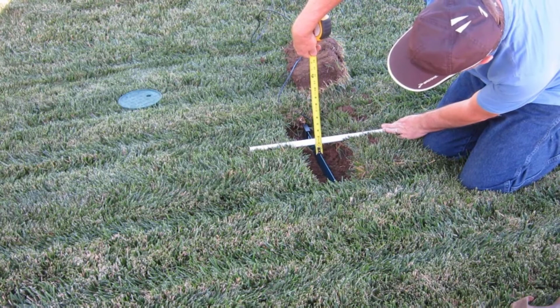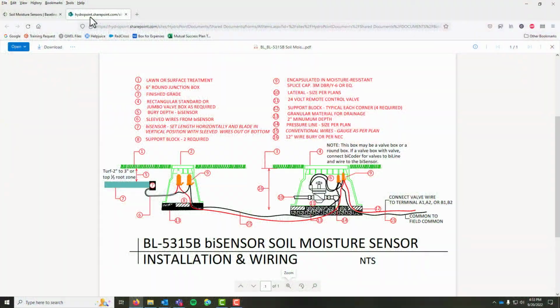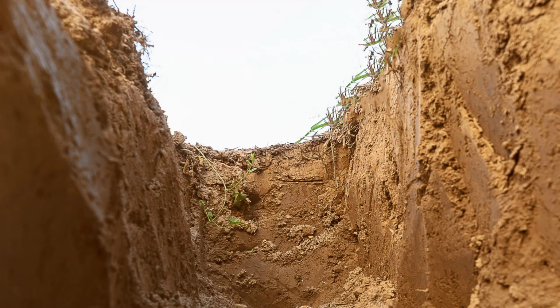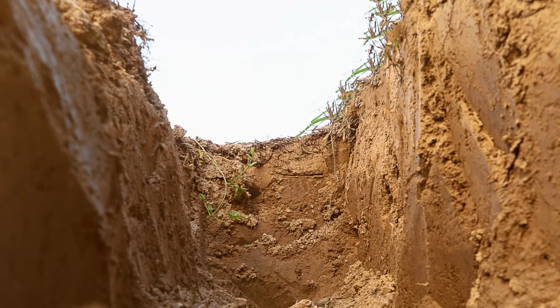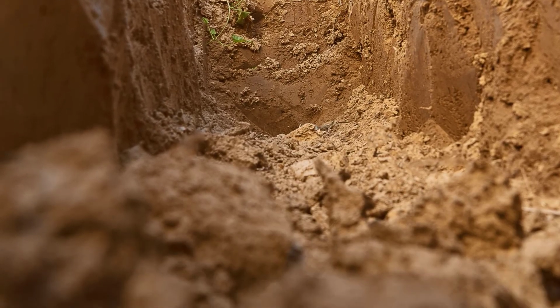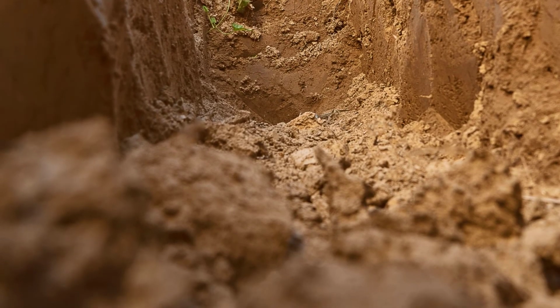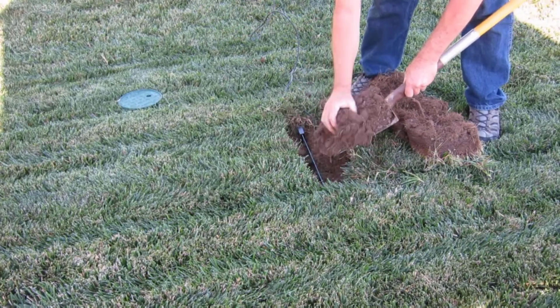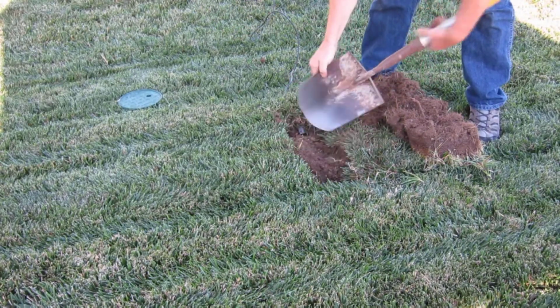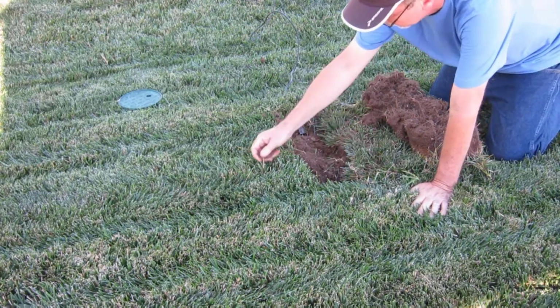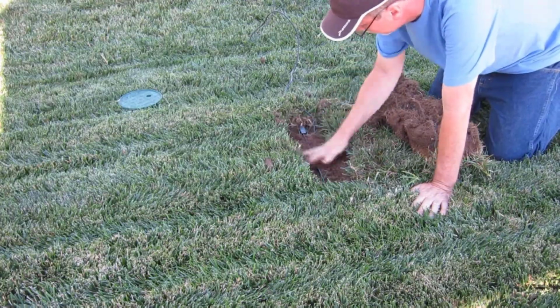The installation details that came with the sensor or what's on the baseline website indicate only a few inches of soil cover over the sensor if it's in turf. Installing a sensor 2 feet deep in clay soil won't see much moisture change and can lead you to think there's a problem when it's just about the installation depth. Did the sensor have soil touching it on all sides? Air pockets or rocks touching the sensor result in inaccurate readings too.